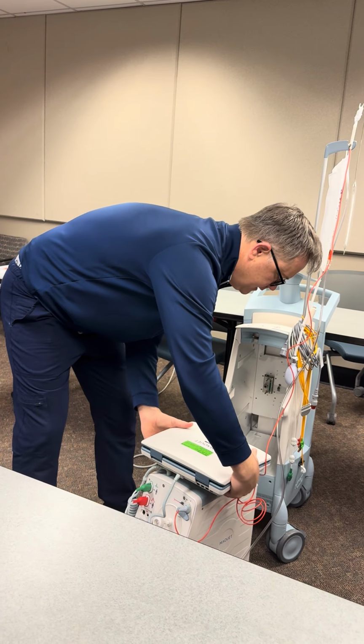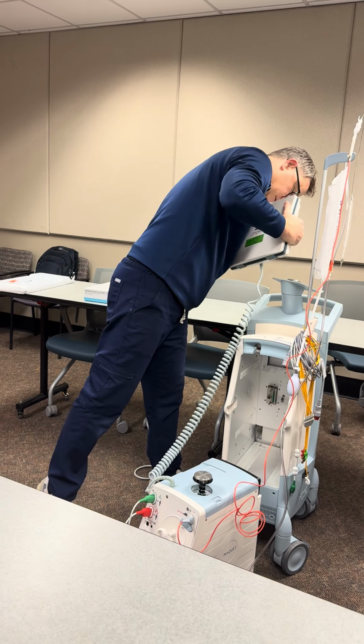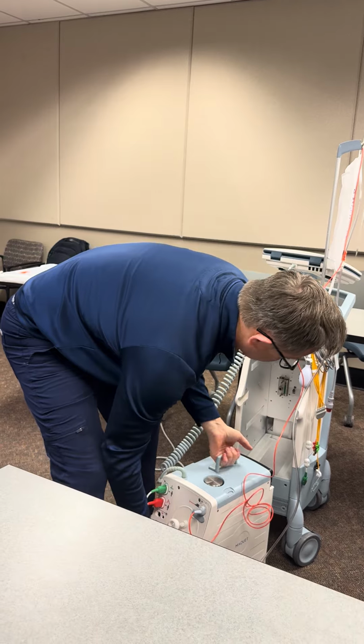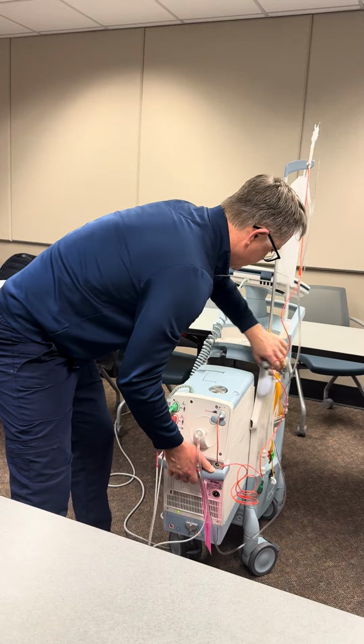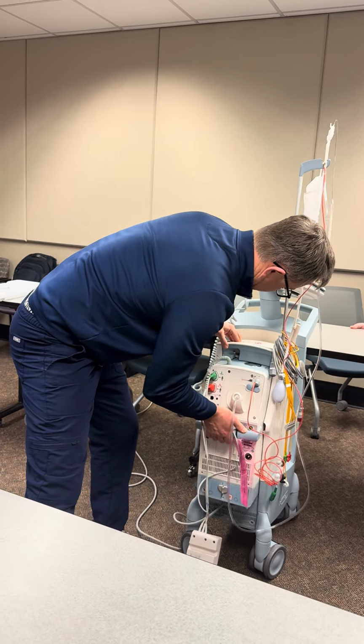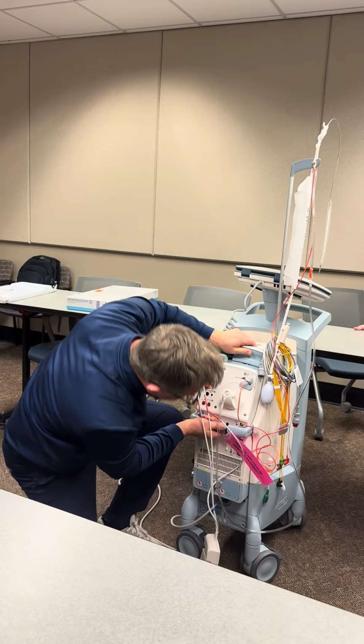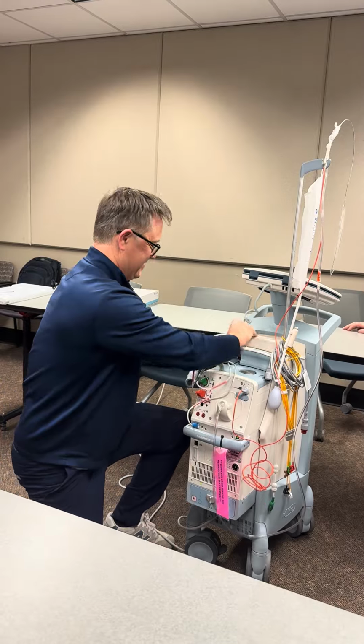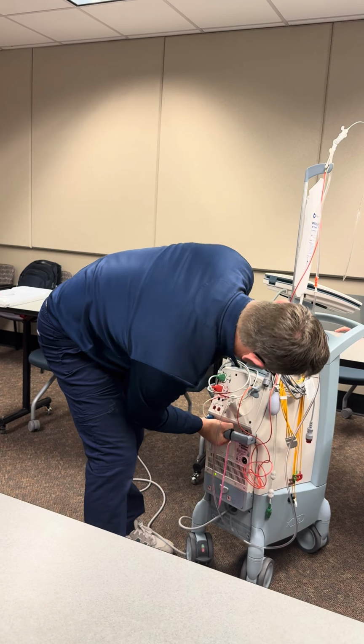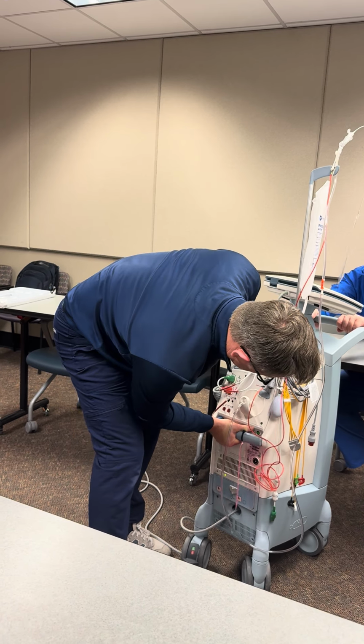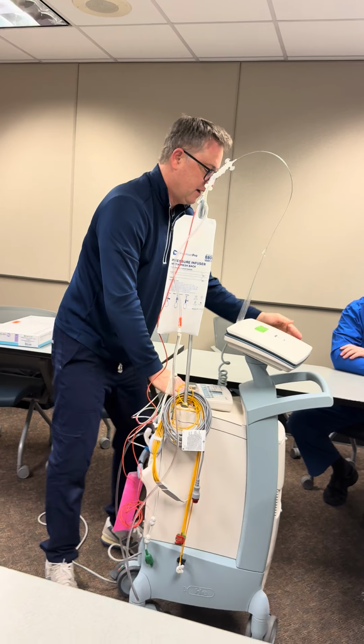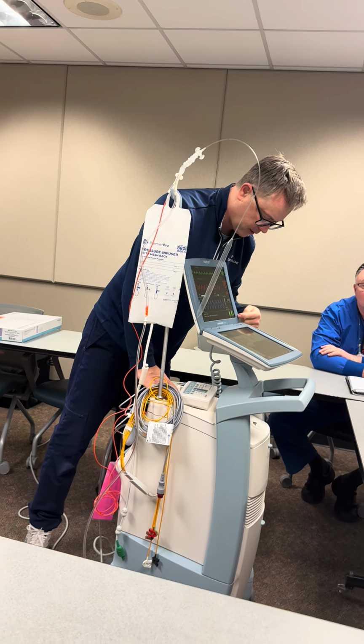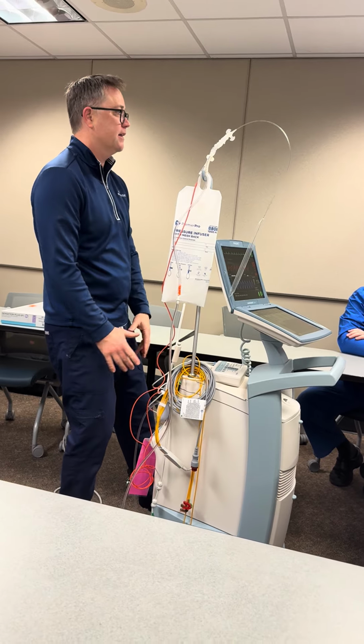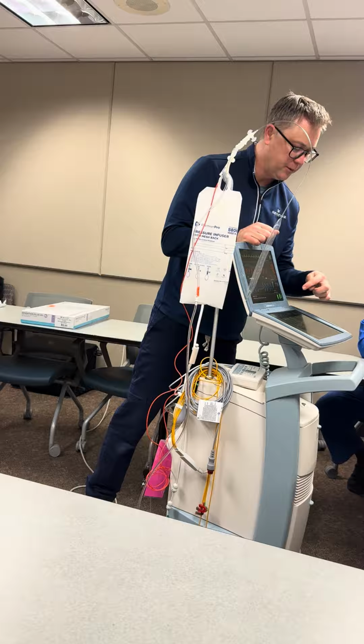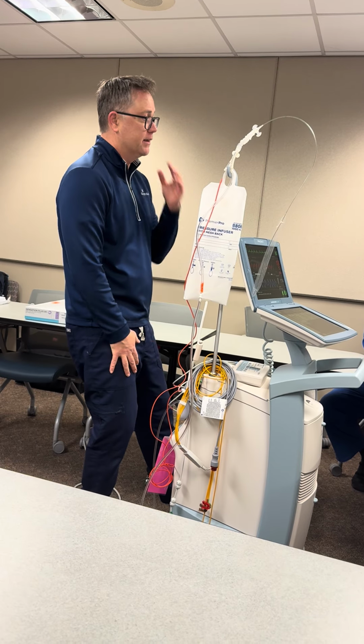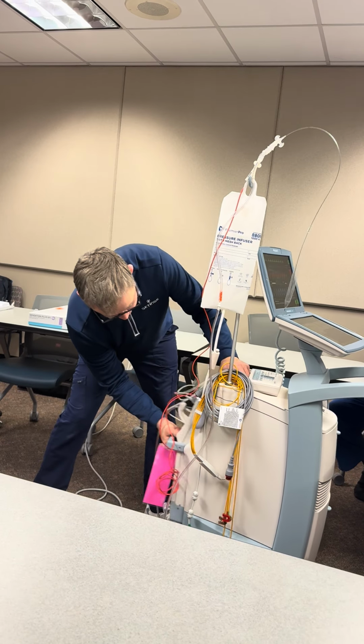And what has happened is somebody comes and kind of does one of these. Looks like it's all put back together. This thing's in a closet, and you go to start it up, and you start getting low battery alarms, and you're not sure why. It's because they didn't dock. Even though it looks like it's all been put back together, they didn't get this transport unit all the way back in. We're still in the rescue mode, and when you're in the rescue mode, you're on battery power. So even though we're plugged in, we're not charging those batteries. So you always want to make sure that, and yours is kind of sticky here, it looks like.